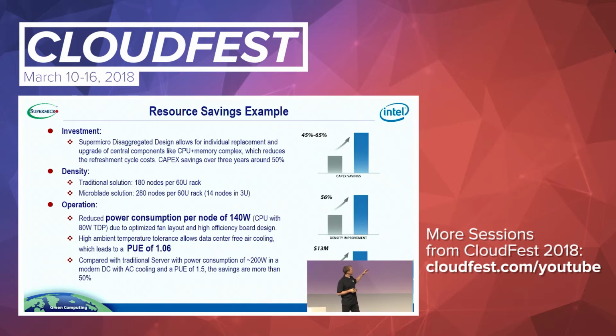The high ambient temperature tolerance of the server, 40 degrees, allows for free air cooling, which means there is no need for additional air conditioning or additional cooling. The entire data center in which this installation is hosted has a PUE of 1.06, so there's almost no additional energy needed for the cooling.